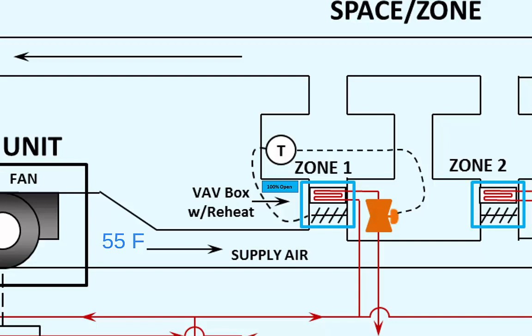Initially, since the damper was fully open, we will start to overcool the space a bit. The controller would recognize this drop in space temperature below set point and command the VAV box damper to start closing. If the cooling requirements continue to drop, eventually the VAV box damper will reach its minimum position. Again, we dictate a minimum position to both ensure minimum ventilation requirements are being met, as well as to allow for a path for a minimum amount of air to flow so we don't deadhead the fan.